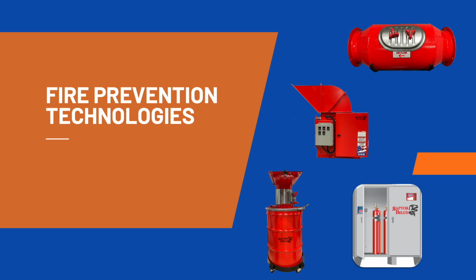So as far as fire prevention technologies, we can do many different things, including if you have return air applications, we can provide abort gates depending on if it calls out for that in the NFPA. If you're returning air back into the building, basically what the abort gate does is it shuts off that side of the duct and it prevents fire, smoke, burning material from entering the building. We also offer explosion-proof drums, which basically protect and isolate the bottom of the hopper discharge from the dust collector or the vessel that you're trying to protect. Spark traps, which would be placed inside ductwork, and CO2 fire suppression systems, which we install inside of the collector or vessel that you're protecting. And basically it shoots CO2 and suffocates the fire. Next slide, please.